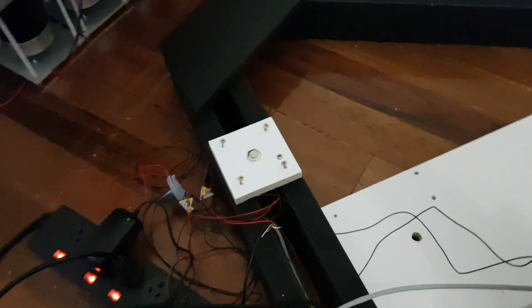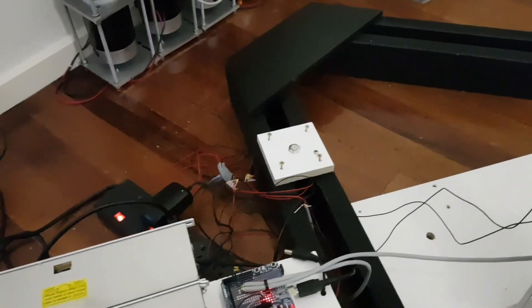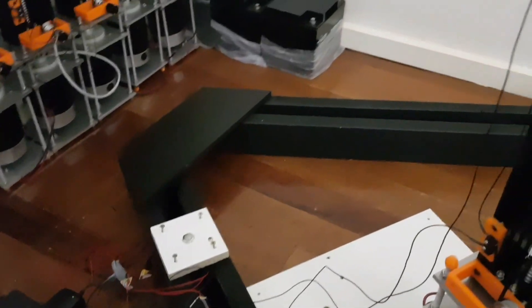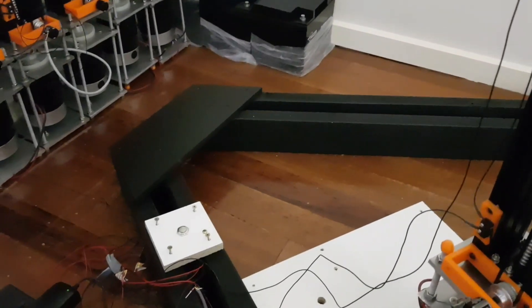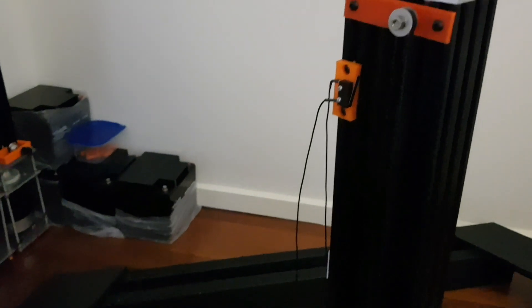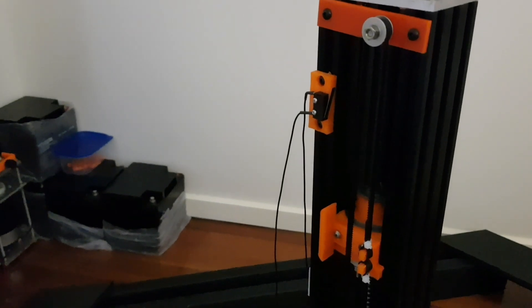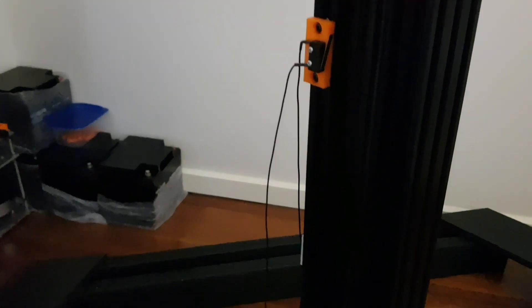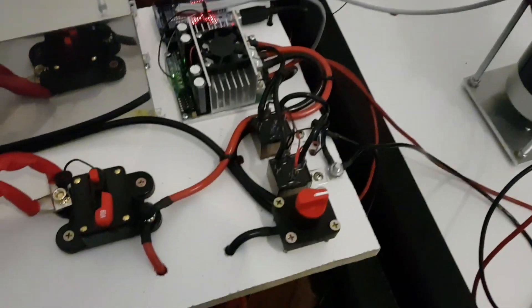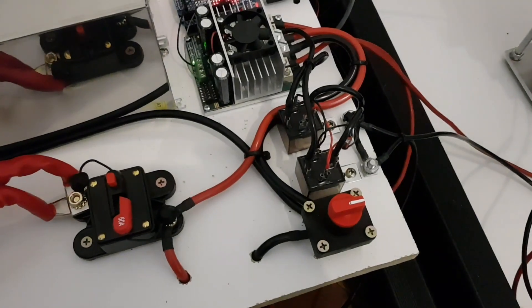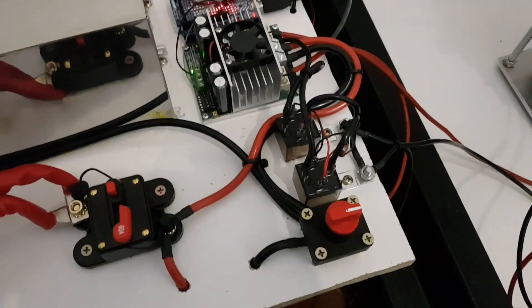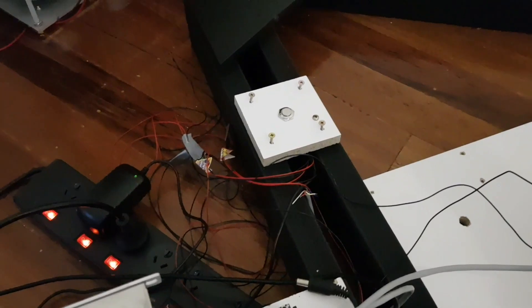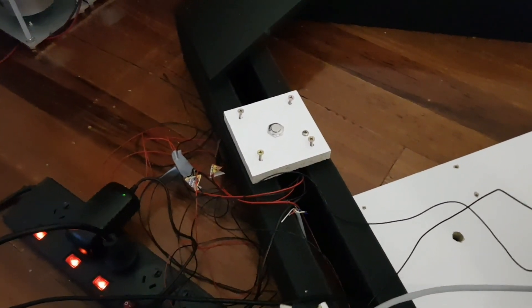That's basically the start switch. So that when one of these limit switches, one of these limit switches are hit, it drops the relay out. So this relay now is unpowered and the circuit won't start again until I push the self latching button.